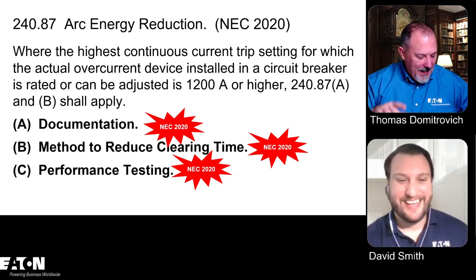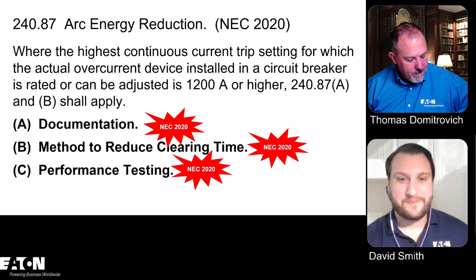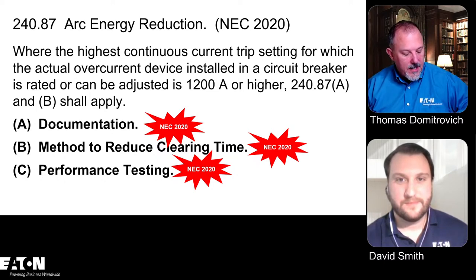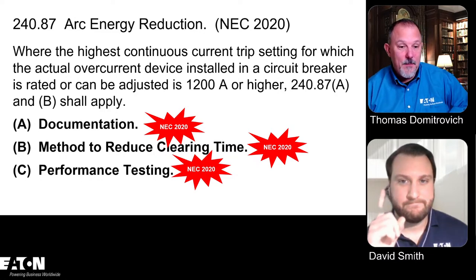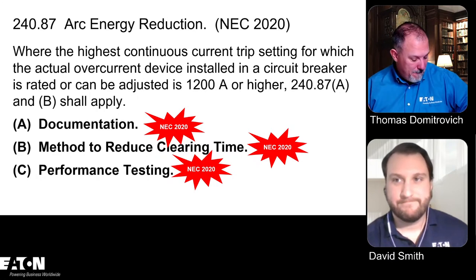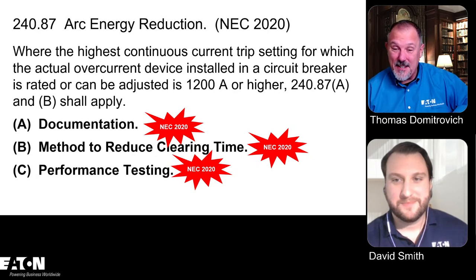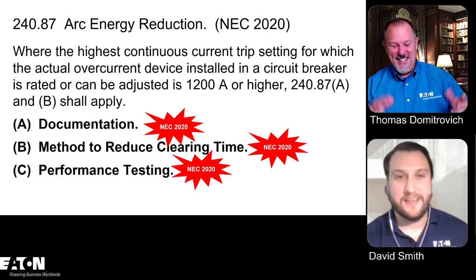So in the documentation, it says documentation, and we're going to cover this too, but documentation shall be available to those authorized to design, install, operate, and inspect the installation as to the location of the circuit breakers. Documentation shall also be provided to demonstrate that the method chosen to reduce clearing time is set to operate at a value below the available arcing currents. That doesn't pick up, though, the, I guess, you could stretch it to C. I'm very flexible, so I would stretch it to that point.